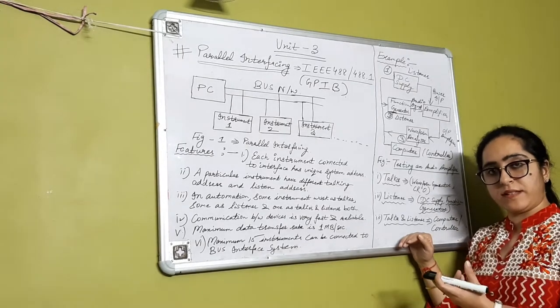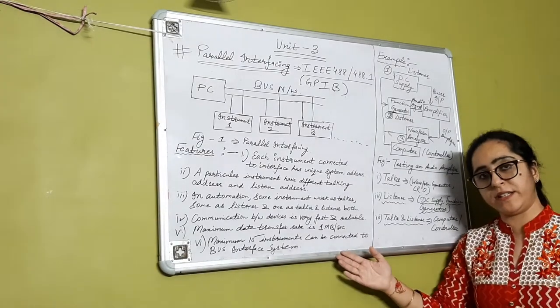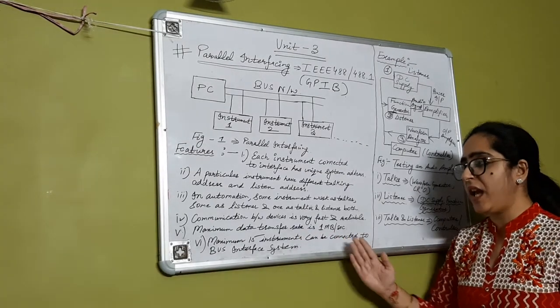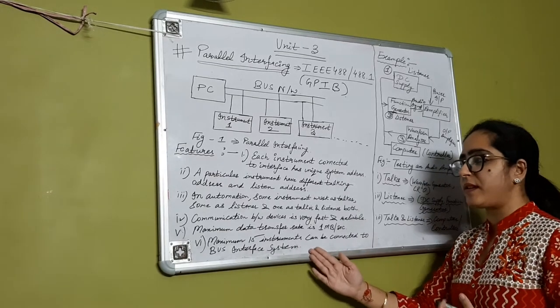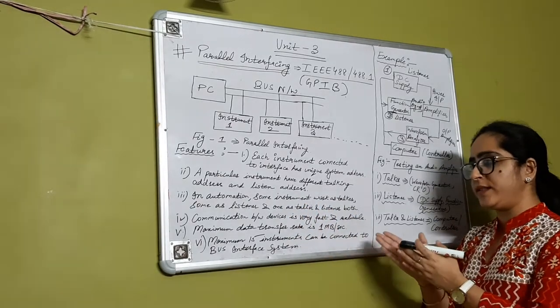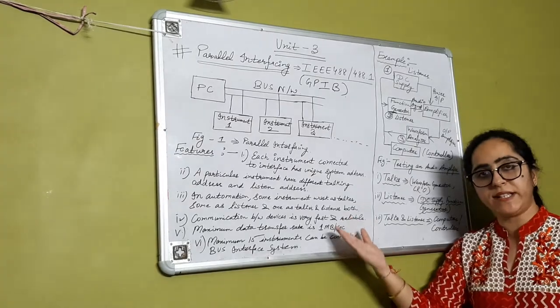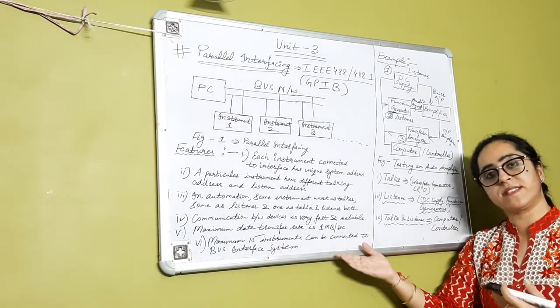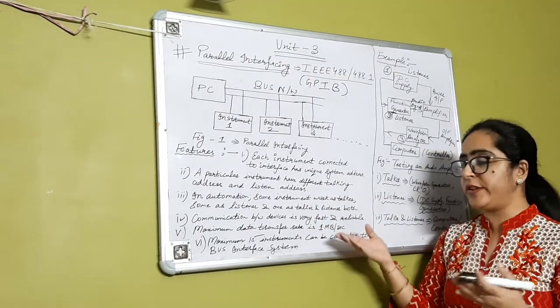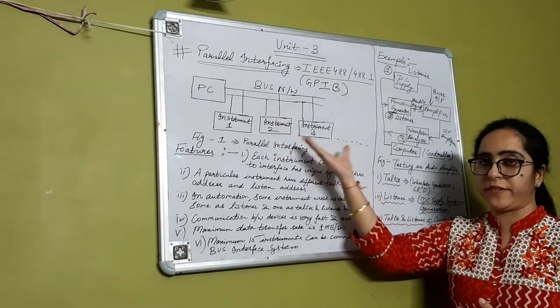In this way, the IEEE 488 bus system works. The advantages of this network: it is very easy to set up and reconfigure, the data transfer rate is 1 megabyte per second, a maximum of 15 instruments can be connected on the bus interface system, and it can work in automation where some instruments work as talker, some as listener, and some as both. They have different talking and listening addresses, and the hardware interface reduces hardware as all devices can be connected on a single interface system.